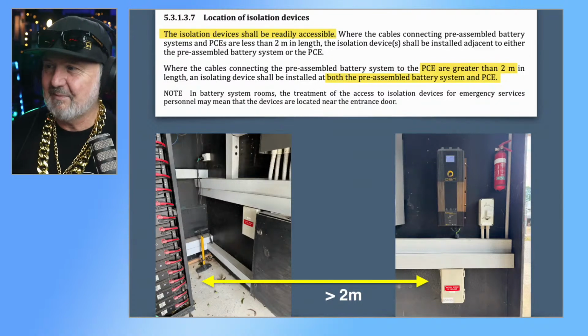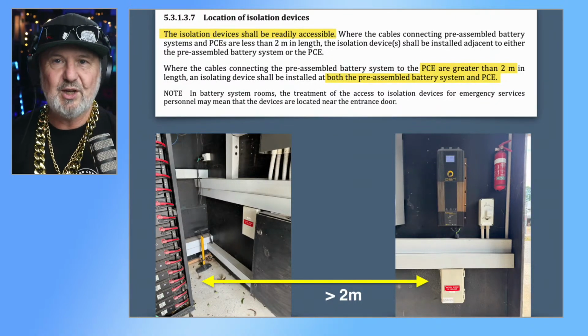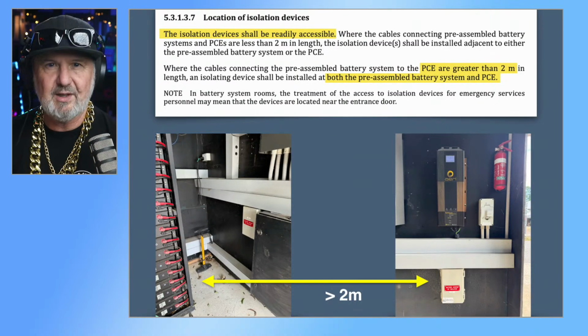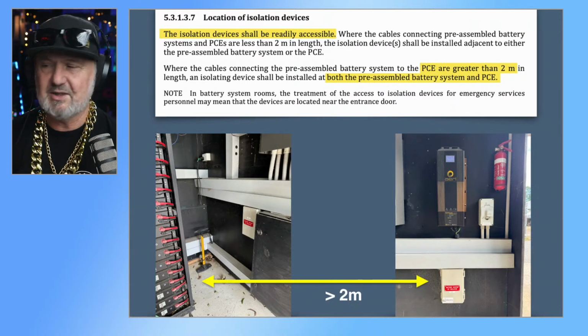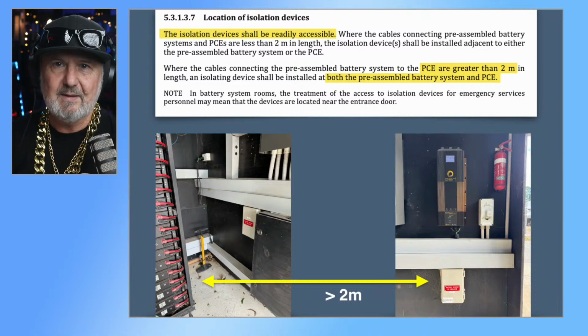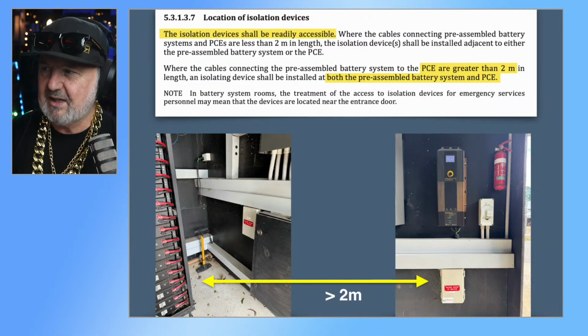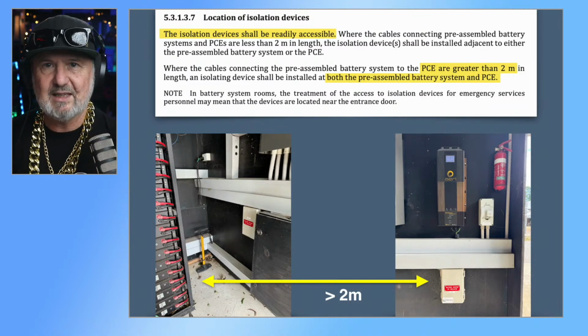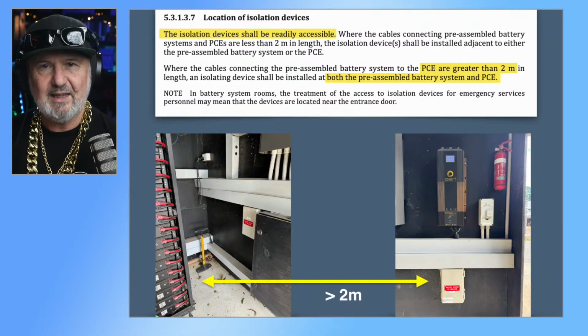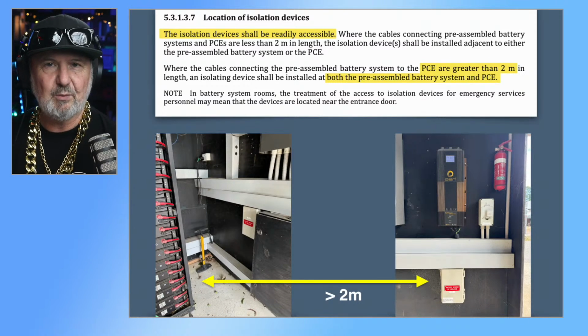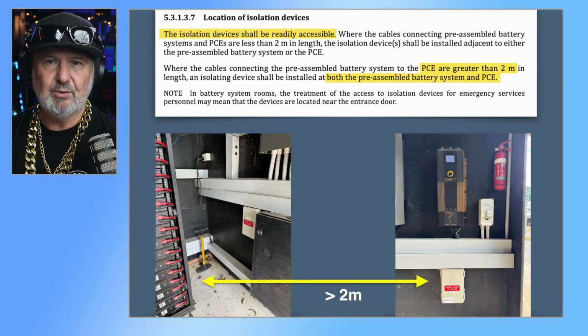All right, so back to isolation. Switching over to isolation now. So we'll be talking about overcurrent, system cable design, and isolation, sort of back and forth a bit. So isolation, the isolation devices shall be readily accessible. Now, the term readily accessible is defined in our wiring rules, AS/NZS 3000, and it means without disassembly or removal of parts.